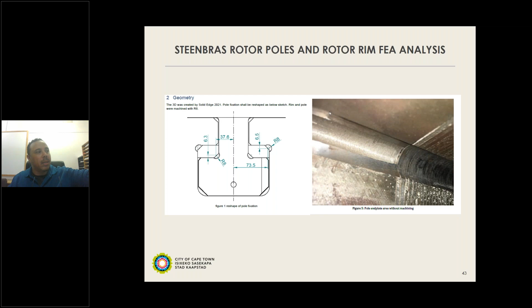On the right hand side are the cracks I'm referring to in the rotor hub, which became a concern on all the machines due to aging and stresses. With the help of Voith in Europe, they looked at all of this for us and redesigned the contour as I showed. If you look at the photo on the right, that groove running through the middle didn't exist before. At a high level, that basically moved the stress points around within the machine.